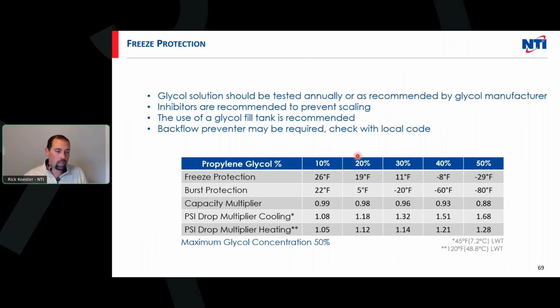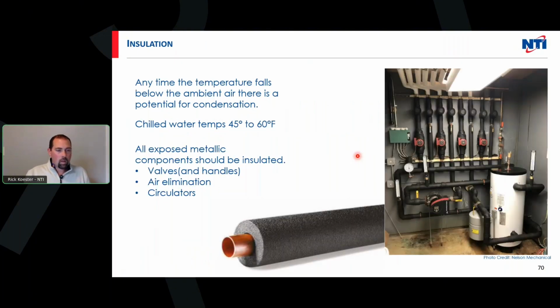We do have some internal protection for when there is electricity. In normal operation, the system has the ability to watch outdoor temperature and the water temperatures. If they start to get too cold, it'll either turn the circulator on, or turn the circulator plus the compressor on, just to make sure we have some flow and some hot heat going through the system. We're not going to overheat it, but it's just enough to prevent any type of freeze. So we want good insulation and good glycol concentration, and the system will be fine.